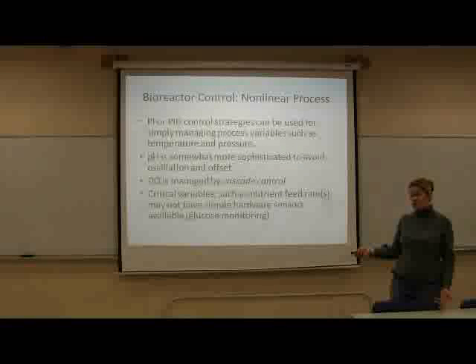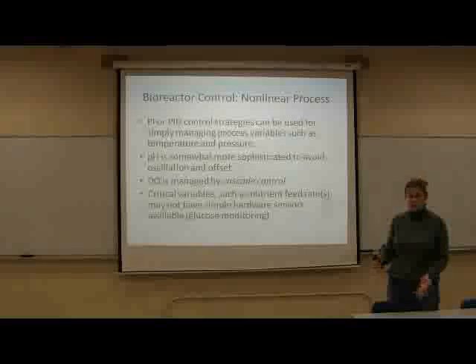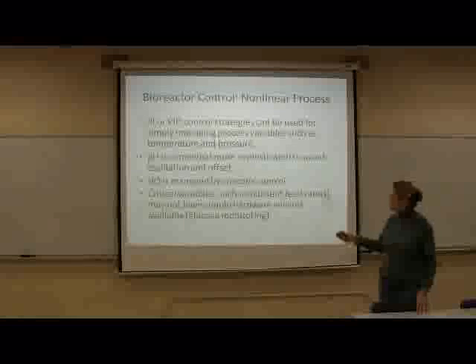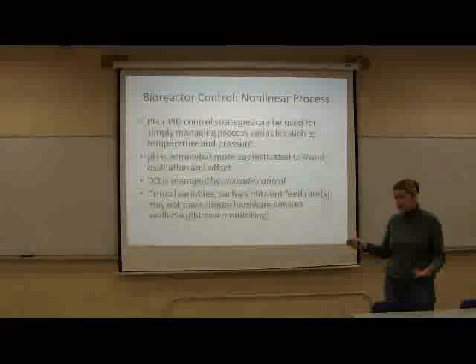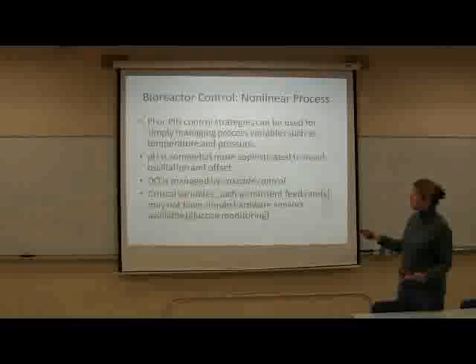Fermentation is a very non-linear process. The things that go on inside the bioreactor are sensitive to a number of different parameters, and the growth is very particular. We're not dealing here with a chemical reaction that does the same thing every time — these bacteria are alive, and sometimes it seems like they have a personality. So the type of control that we need to use is very sophisticated. We use standard control for temperature. The pH uses a very sophisticated control model designed for pH control in solutions, with very little offset — partly due to the fact that we have a buffer in our media — making it a very good pH control mechanism in the system.